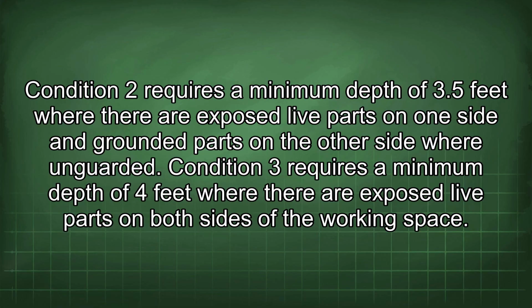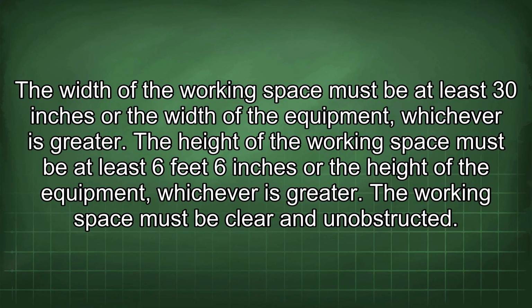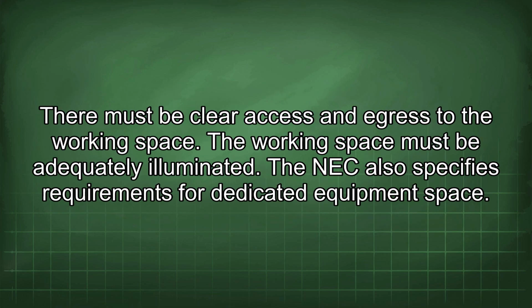Condition 3 requires a minimum depth of 4 feet where there are exposed live parts on both sides of the working space. The width of the working space must be at least 30 inches or the width of the equipment, whichever is greater. The height of the working space must be at least 6 feet 6 inches or the height of the equipment, whichever is greater. The working space must be clear and unobstructed. There must be clear access and egress to the working space. The working space must be adequately illuminated.